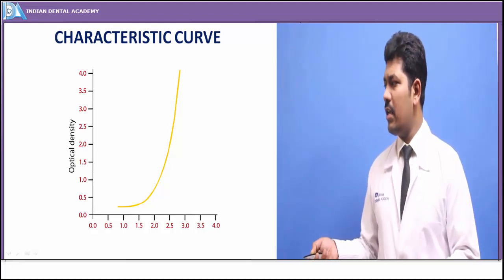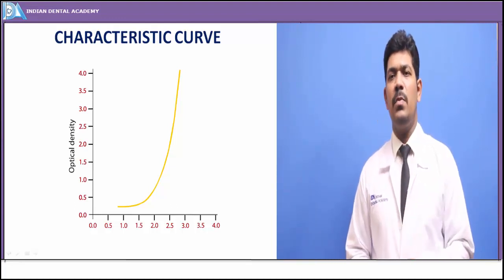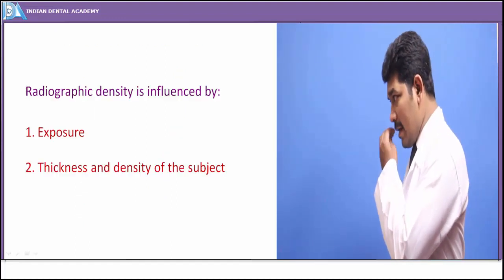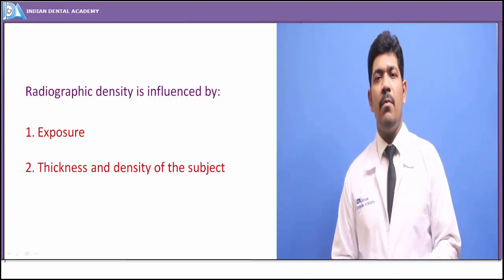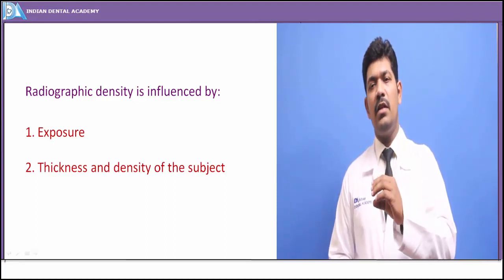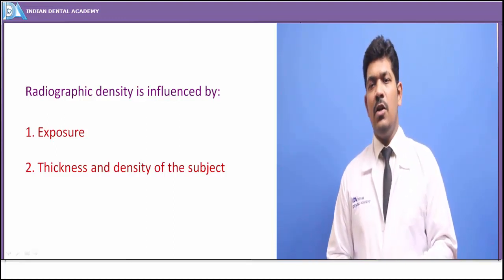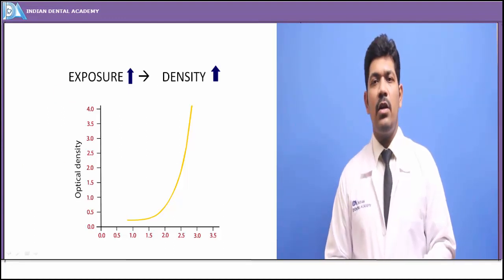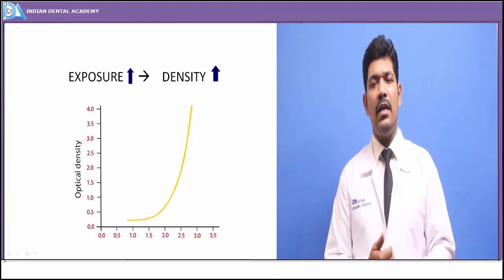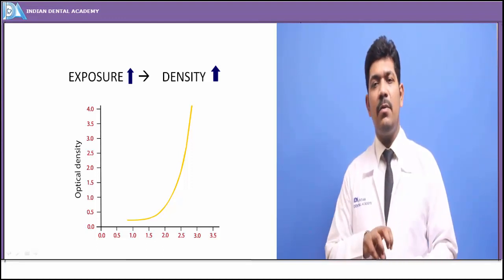The characteristic curve is based upon the log ratio of light incident to light transmitted. This is the optimal characteristic curve required for any kind of radiograph, be it E-speed, F-speed, or any speed. Radiograph density is determined by two factors: one is the exposure — the amount of radiation the image receptor is subjected to — and the other is the thickness and density of the subject.